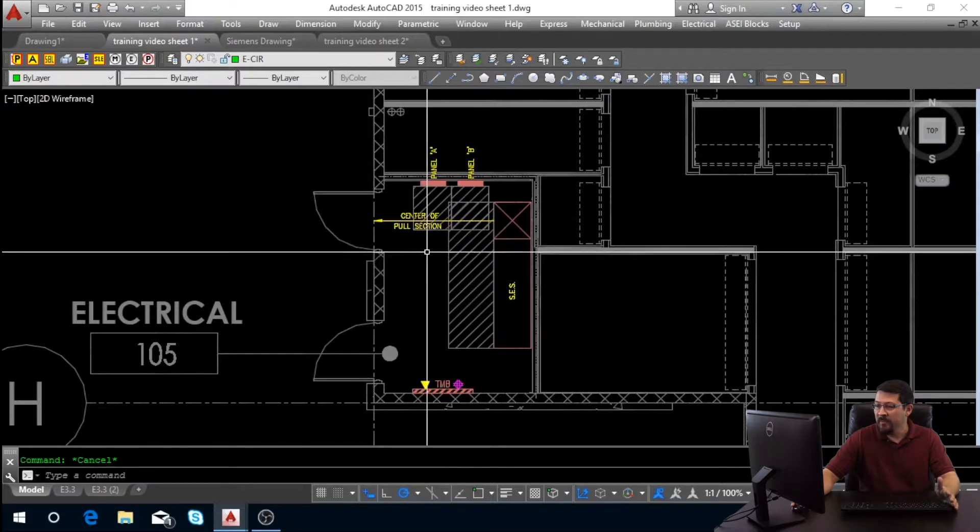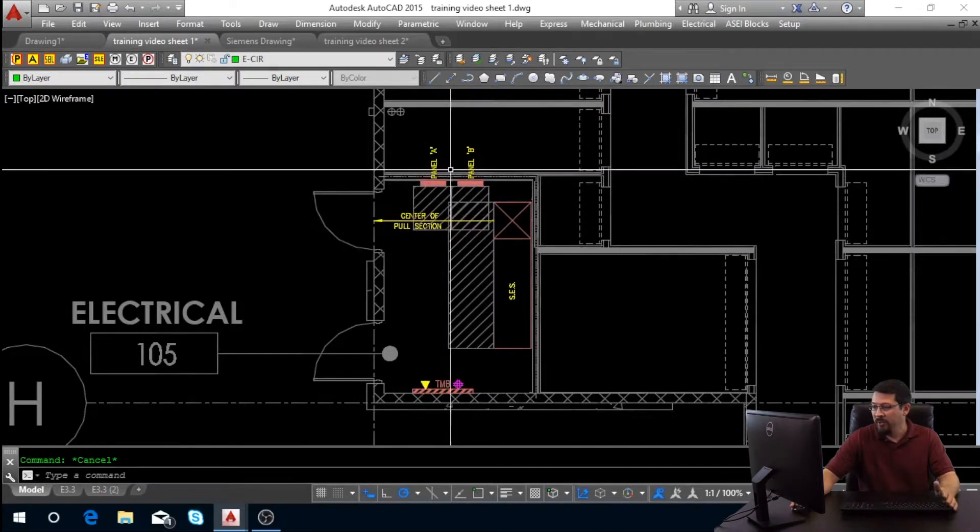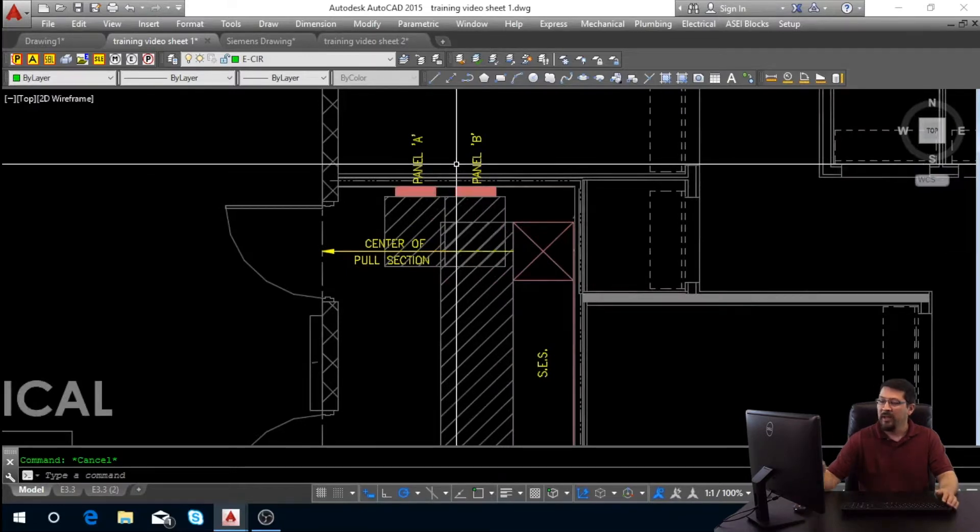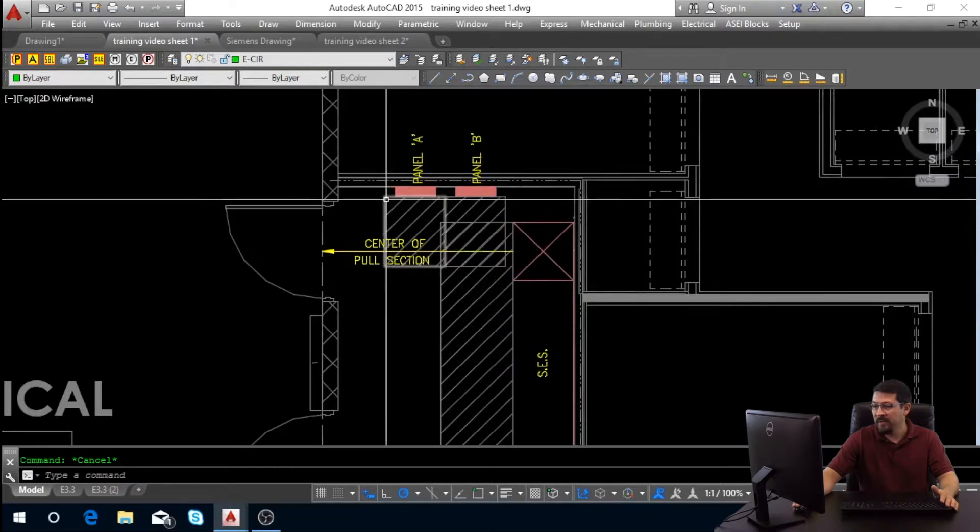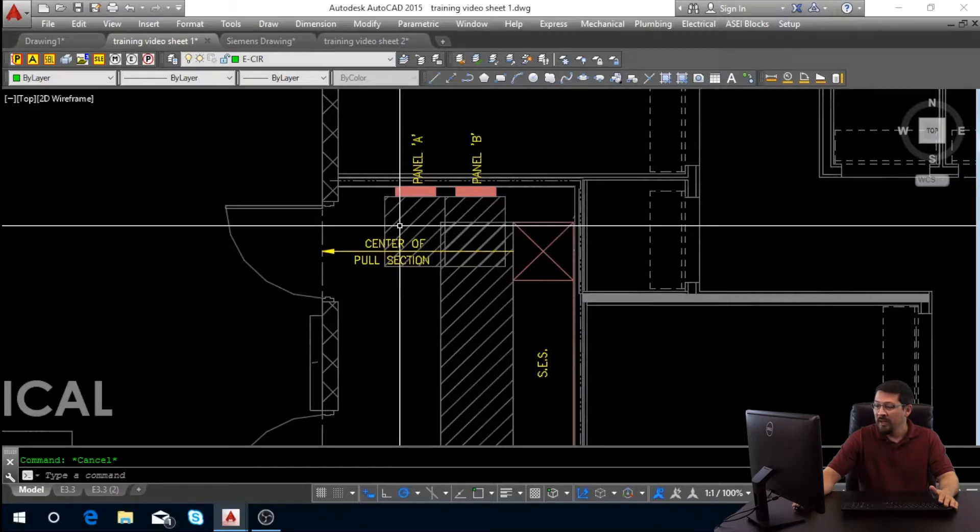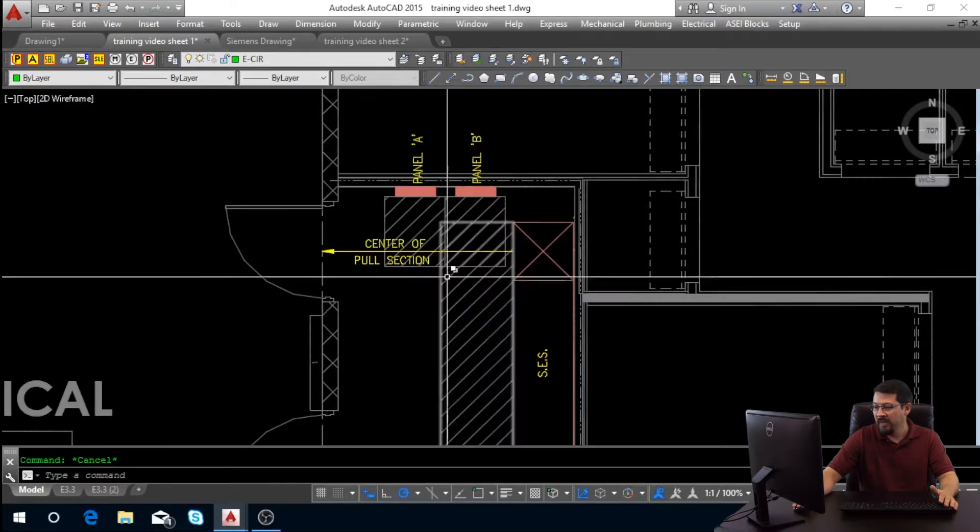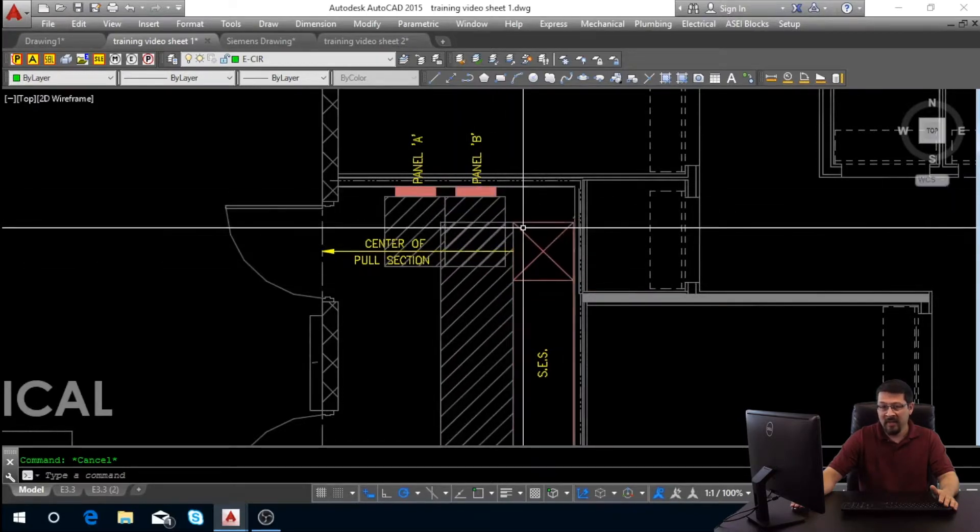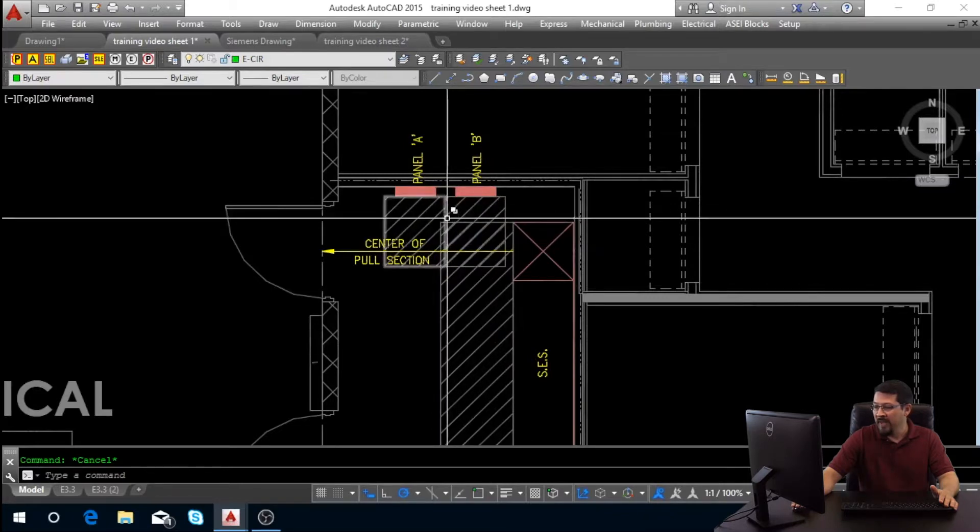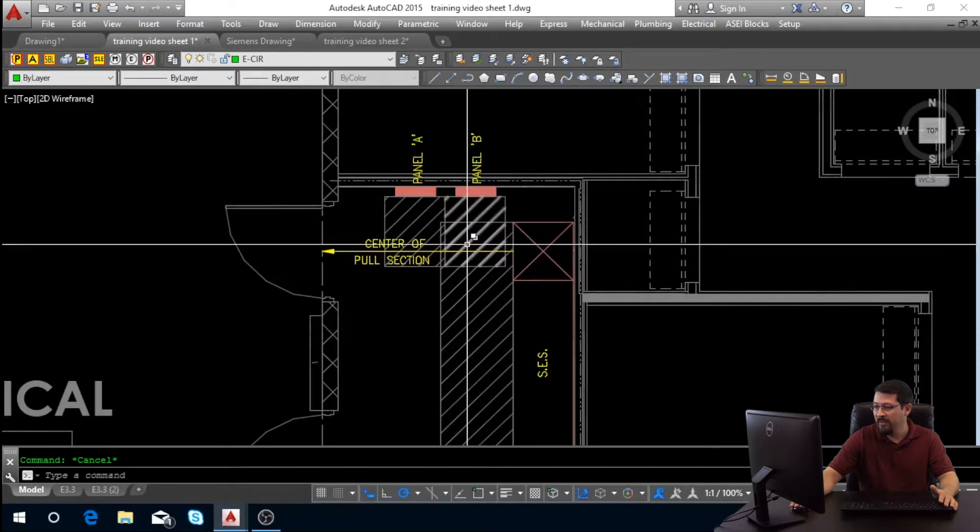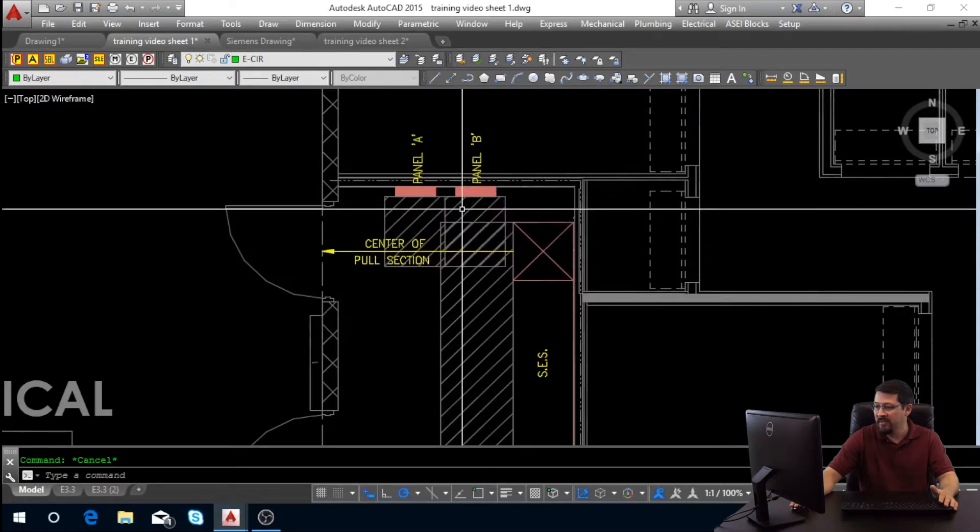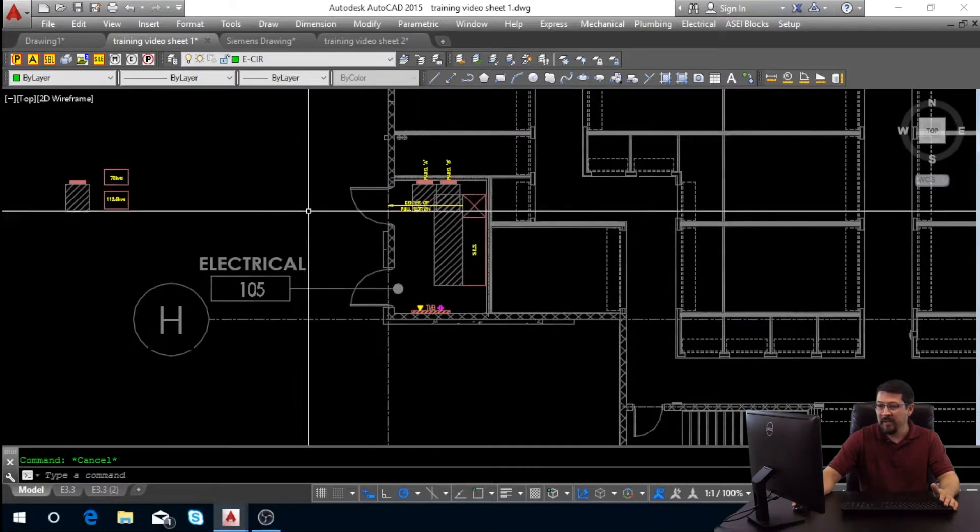Now we come into panels, bringing your panels in. If you have one or two, for this one I've just shown two. Basically what you have is a working clear space of 30 inches wide by 36 inches deep. And what I have done is I've shown that the clear spaces can be shared between panels and the S.E.S.. There's nothing wrong with that. Just as long as the person working on the panel has no interference there in that space. That's good.